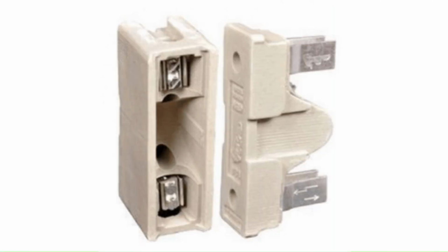The rewirable fuse is mostly used in small circuits or for domestic wiring. The fuse case and the fuse carrier are the two main parts of the rewirable fuse. The base of the fuse is made up of porcelain and it holds the wires, which may be made up of lead, copper or aluminium. The fuse carrier can be easily inserted or taken out of the base without opening the main switch.